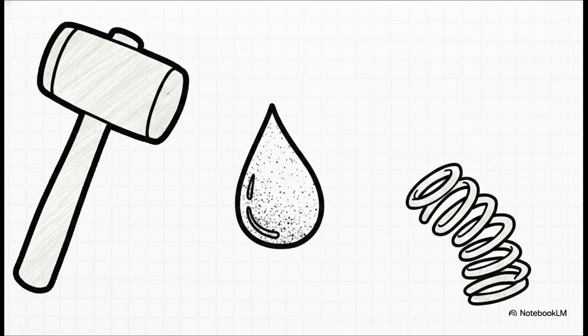But on the flip side, it's a pretty blunt instrument. Its main limitation is that it provides very limited diagnostic information, essentially just a binary trip signal. It yells, yes, pressure spiked, but doesn't identify the specific fault type. Also, because it's physical, it's vulnerable to dirt or moisture in the oil. And that spring can suffer from material fatigue or spring drift over its 10 to 20-year lifespan, which means it requires regular testing to make sure it's still perfectly calibrated.